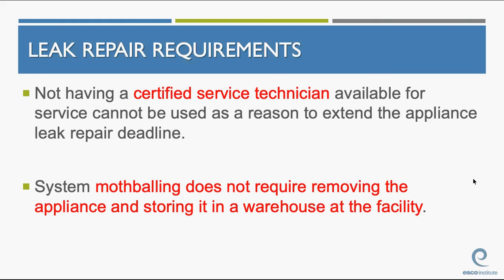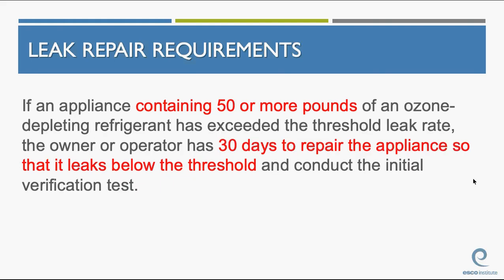Not having a certified technician available cannot be used as a reason to extend the appliance leak repair deadline. They put this again in red print because it's important. Not having a certified service technician available does not excuse them from meeting the leak repair deadlines. System mothballing does not require removing the appliance and storing it in a warehouse at the facility. You can mothball an appliance right there while you're using it. It does not require removing the appliance and storing it in a warehouse. It can be mothballed in place.